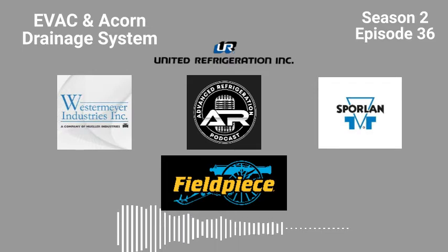So you're going to go into these collector tanks. The water collects in there. Then there is a float switch in there. Once the float switch makes, the microprocessor controller says, okay, I have enough water in here, so I'm going to blow down the vacuum. Now it does it by a solenoid valve on the top of the tank. You'll see a solenoid valve with kind of an orifice looking deal on there, like a snubber, just to slow down the flow.